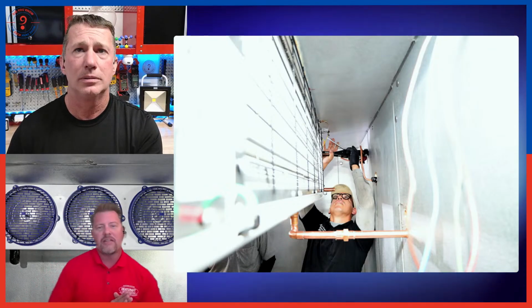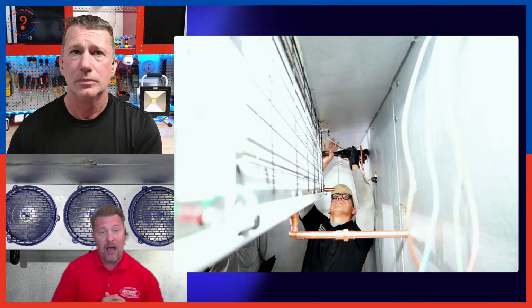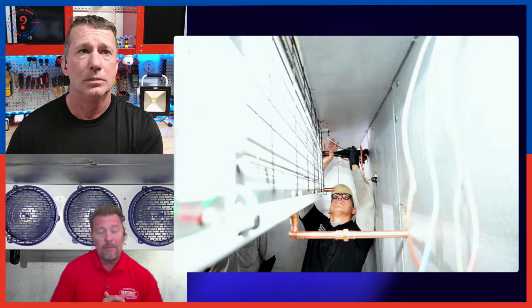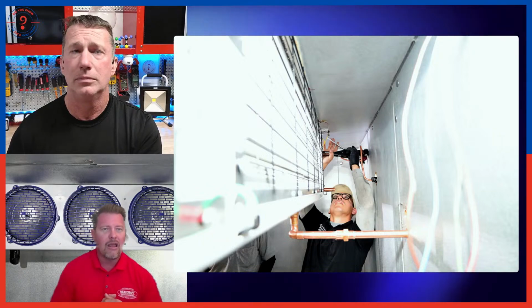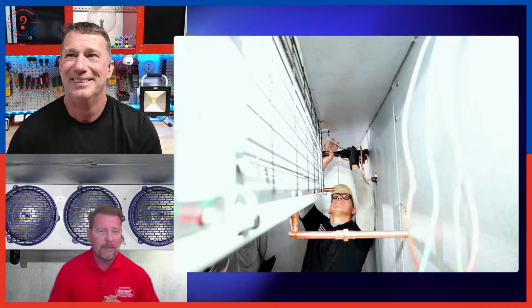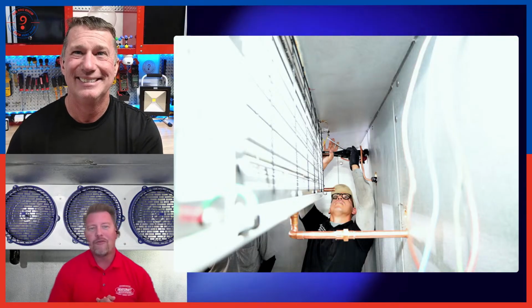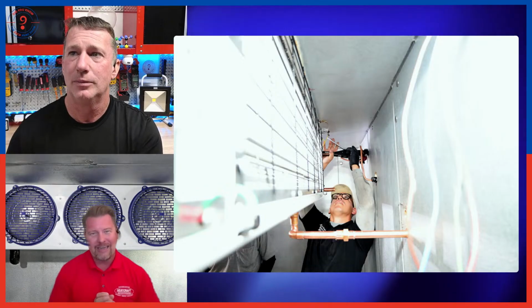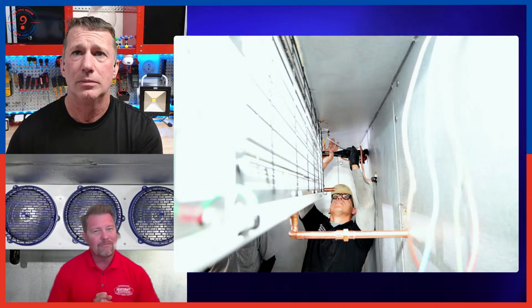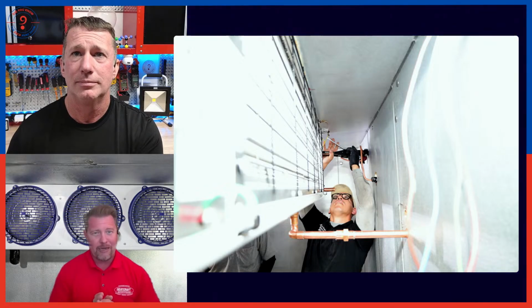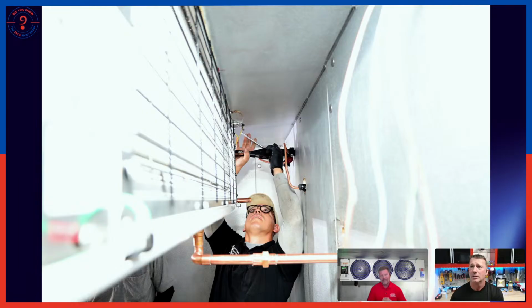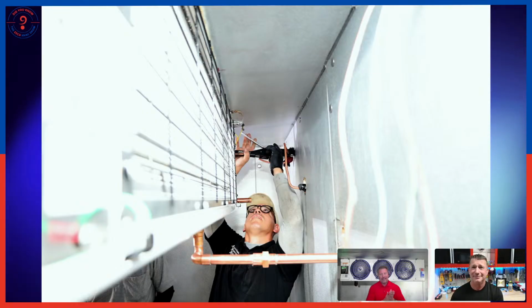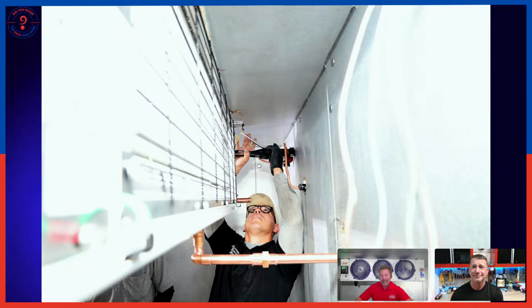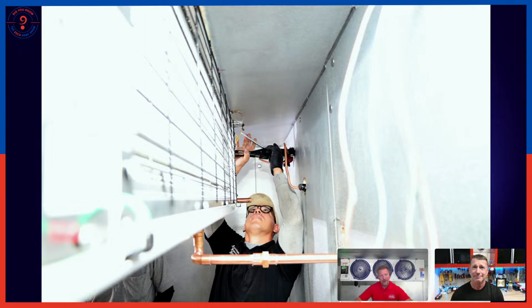So there are subtle differences we're going to notice with A2Ls, other than the obvious that you can see on the coil behind me, a big sticker that says A2L. We can't make it much more plain and simple to people what's in the system. Now, hopefully your installer marks what A2L they put in it. That's a whole other thing, that people tend to forget to mark what refrigerant they put in anymore. When there were only three refrigerants 30 years ago, it wasn't as critical, but it has definitely changed. And to the technicians out there, please mark what you put in your system. It would save us in tech support a lot of time figuring it out, and it's just good practice.